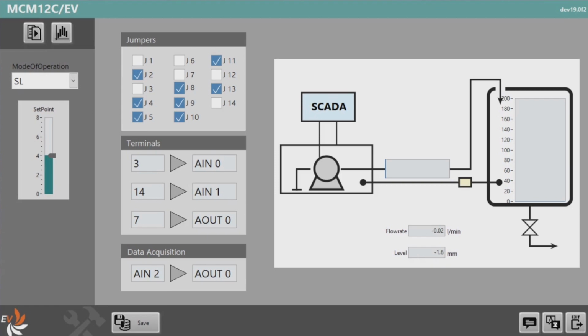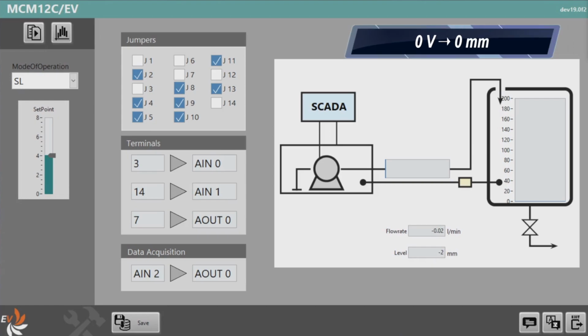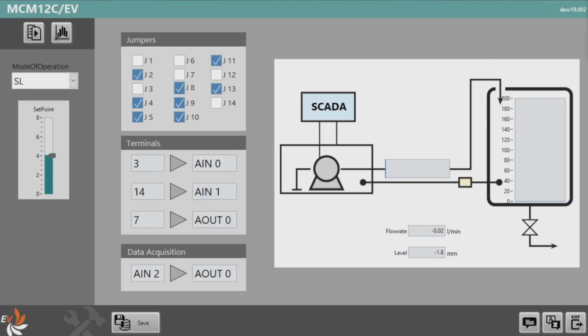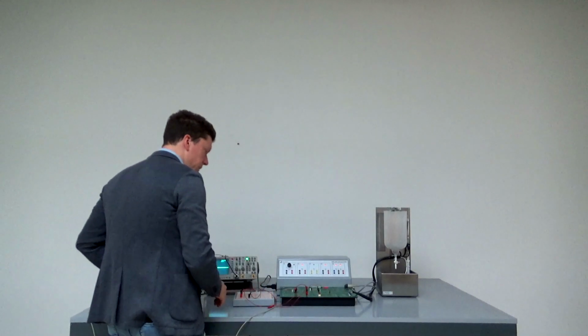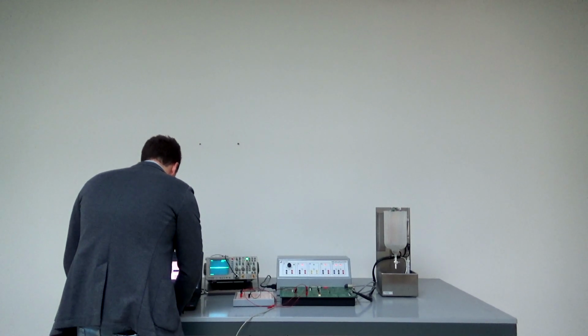Now let's work with a level control. So in my software I can set the set point, which is the level of my tank, and this is mapped on the full range of our sensors. So 0 volt, meaning 0 level, which we have calibrated at the beginning, and then 8 volts, meaning 200 millimeters of water. So with this control up here, you can select the mode of operation. So let's perform SL first, which means level control. Once the model has been powered up, it received the set point. So for example, 4 volts, meaning around 1 liter of water.